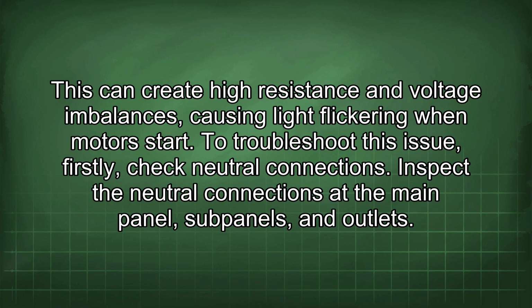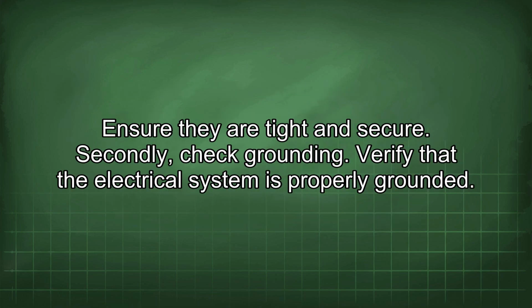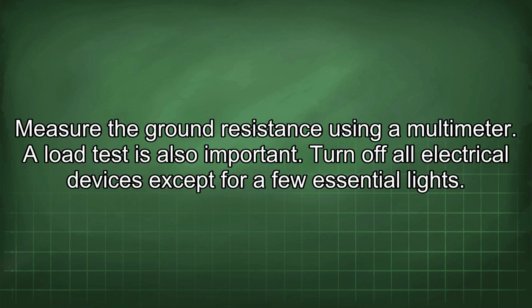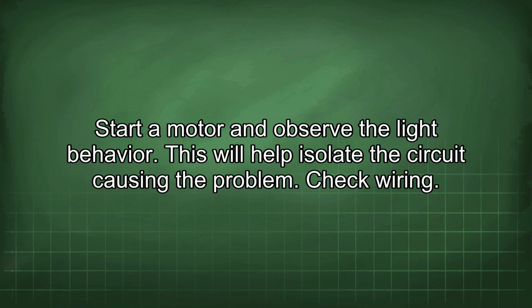To troubleshoot this issue, firstly, check neutral connections. Inspect the neutral connections at the main panel, sub-panels, and outlets. Ensure they are tight and secure. Secondly, check grounding. Verify that the electrical system is properly grounded. Measure the ground resistance using a multimeter. A load test is also important. Turn off all electrical devices except for a few essential lights. Start a motor and observe the light behavior. This will help isolate the circuit causing the problem.